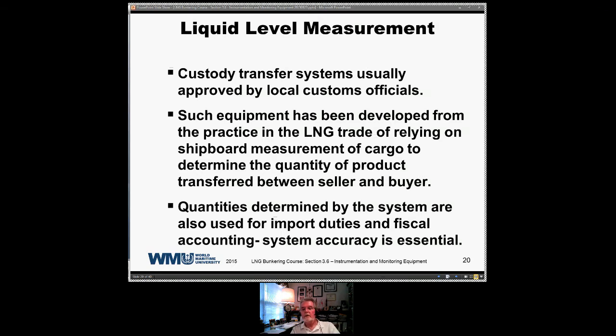So when the ship arrives in a port, it does what is called a custody transfer measurement calculation to determine the volume of cargo that's on board the ship. When cargo transfer is completed, it does another calculation to determine how much cargo remains on board, and the difference is the amount of cargo that has been delivered from the seller to the buyer. These figures are accepted by customs, by the seller, and by the buyer. Quantities determined by the system are also used for import duties and fiscal accounting, so system accuracy is essential. Again, with import duties, this is where customs comes into play. So obviously these systems are very, very accurate and keep all parties involved happy. And that's the important thing.